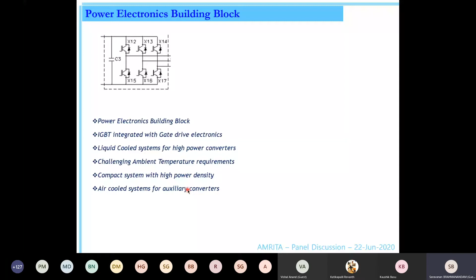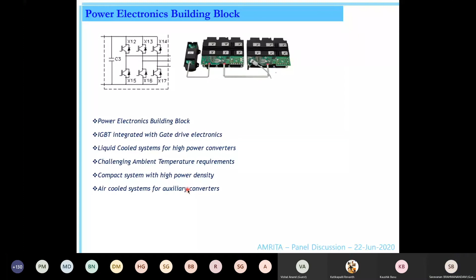In IGBT-based systems, we have the gate driver integrated inside the power electronic block. These are all liquid-cooled systems, dealing with challenging ambient temperatures, and are compact with high power density and air-cooled systems for auxiliary converters. Here the IGBT is a 6.5 kV device with a 750 ampere rating, and you can see how our power building block looks like.